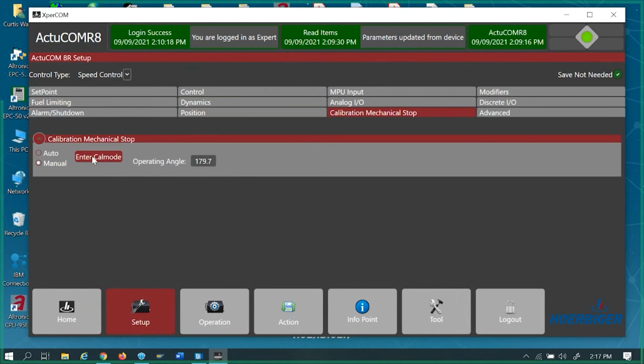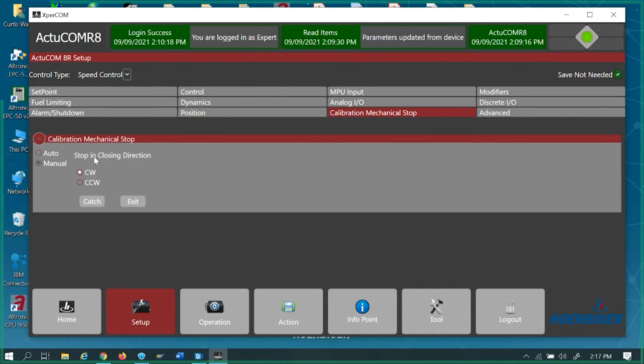So right now, like on this unit I have on my desk, let's see, I think it's on. If I hit enter cal mode, you tell it what position or what rotation you're in. If you picked up this governor and looked at the shaft of it, that's the rotation. If you're looking at the shaft and you turn it to the right, that's clockwise. If you turn it to the left, it would be counterclockwise.